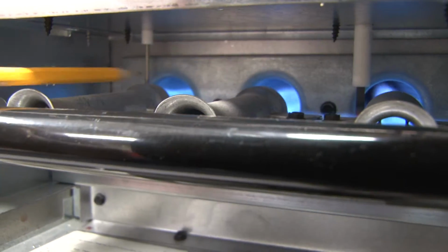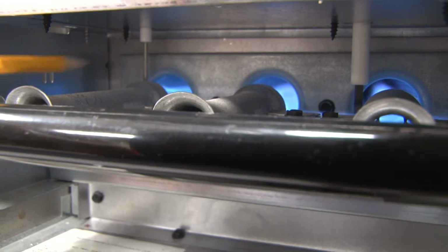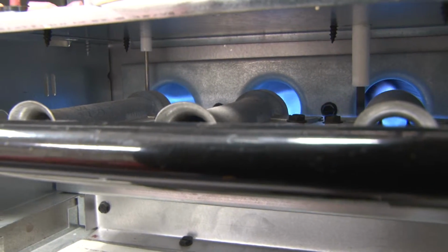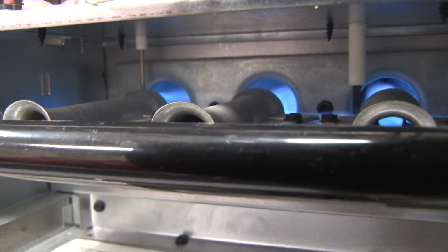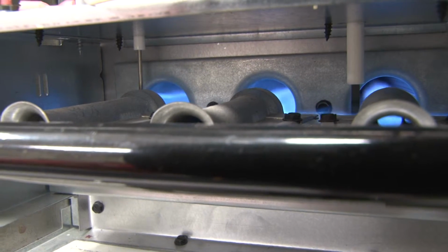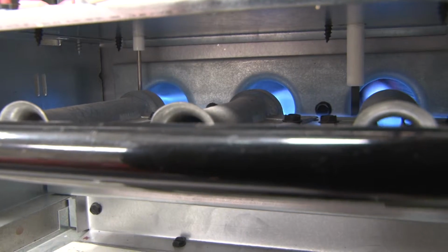The igniter is here, but a sensor is actually in the flame to prove that there is a flame there. If not, it will de-energize the burner circuit to keep it from sending raw gas inside the combustion chamber. That could be very dangerous if it continued to send gas through.